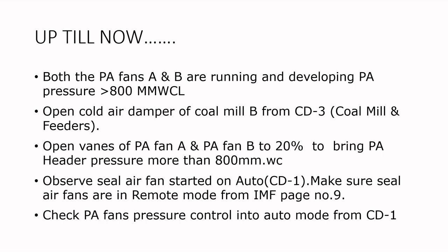Now observe whether the seal air fans have started on auto or not. From CD1, control desk 1, make sure that the seal air fans are in remote mode from the instructor malfunction page number 9, IMF page number 9. Now check the PA fan pressure control, it is in auto mode from CD1 and put on around 800 millimeters of water column. Now the pulverizer ready permissives.